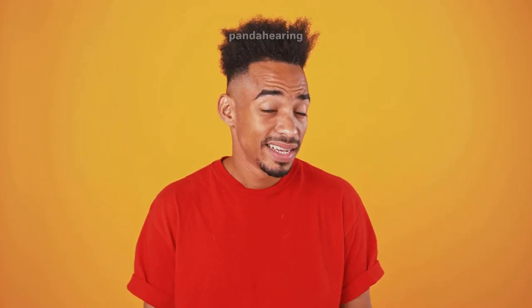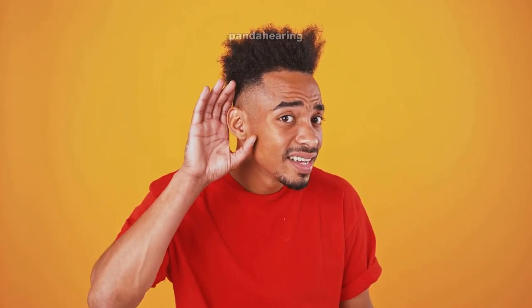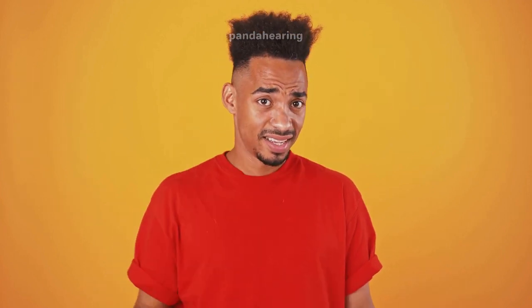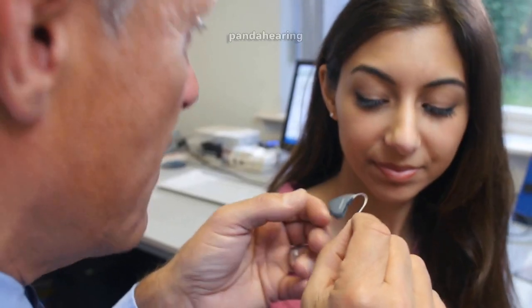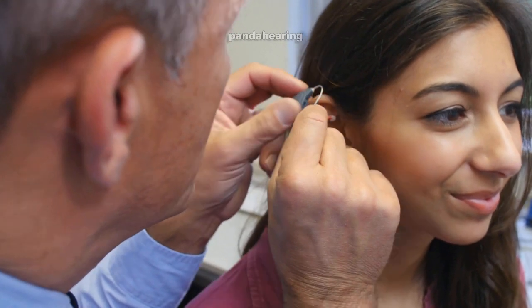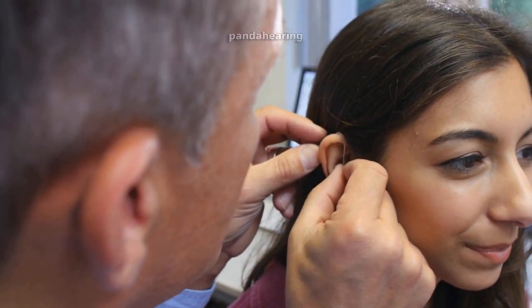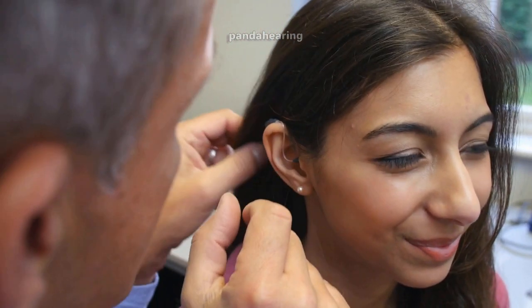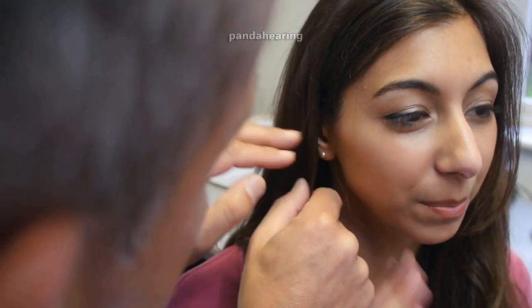What causes feedback to take place? To have a better understanding of why feedback occurs with hearing aids, it is necessary to have some background information. The following is a list of the most common causes of squeaking in hearing aids. Poor fitting. Feedback is an issue that can arise when a hearing aid does not fit properly. A feedback loop is created when there is space between the ear and the hearing aid because the amplified sound that is exiting from the ear mold is then re-entering the microphone.